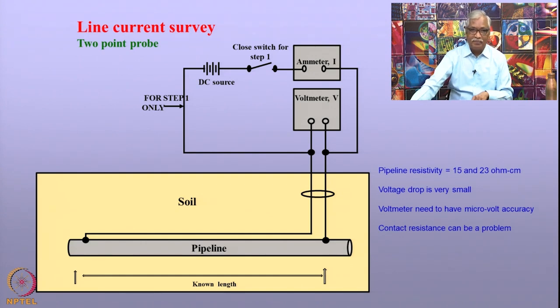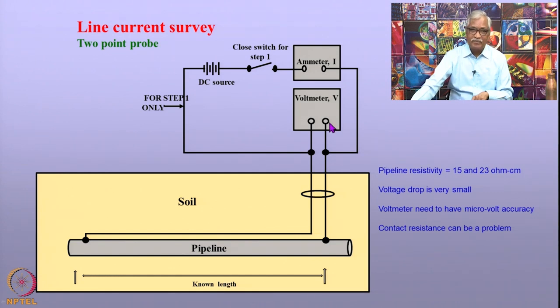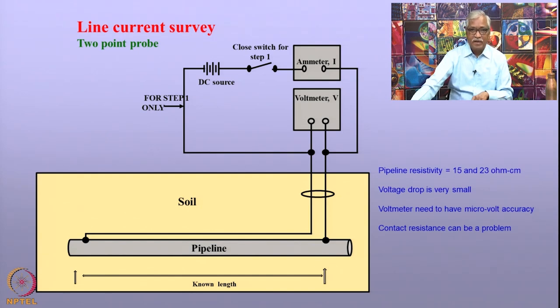However, if the resistivity of the pipeline is not known, an additional circuit is used wherein a known amount of current is passed through the two points using a DC source. By simultaneously measuring the voltage for a known current, it is possible to estimate the resistance of the pipeline in that segment. Generally, pipeline resistivity lies in the range of 15 to 23 ohm-centimeters, so the voltage drop is significantly small and the voltmeter must have resolution in terms of microvolts.